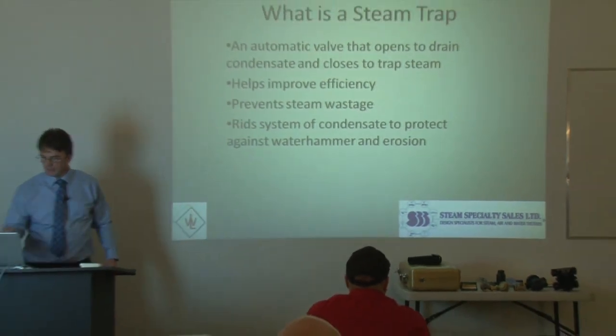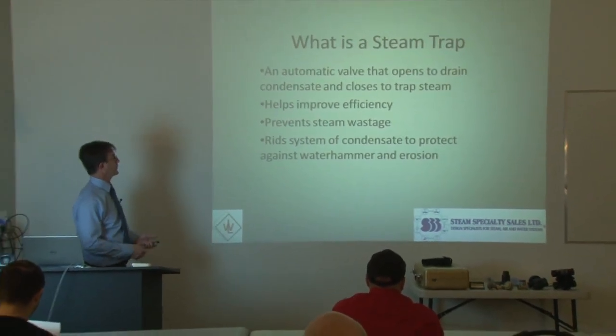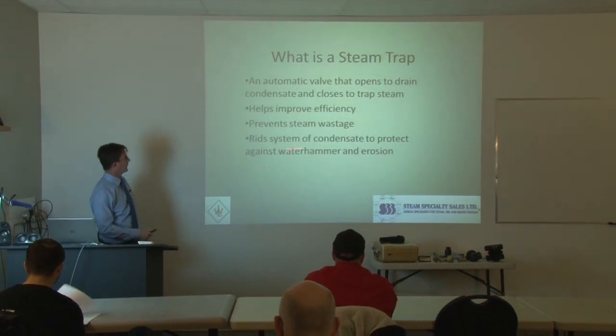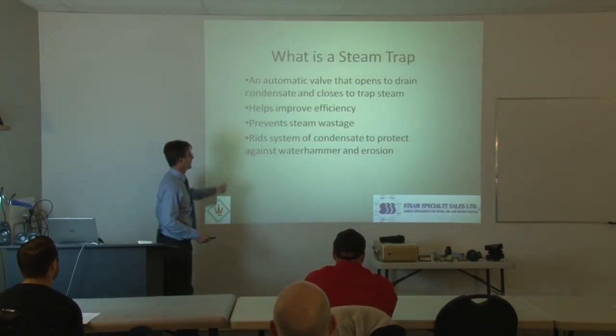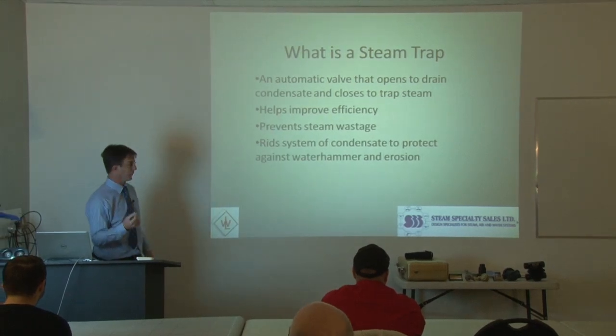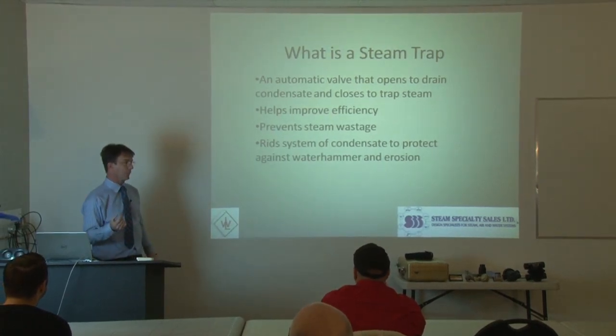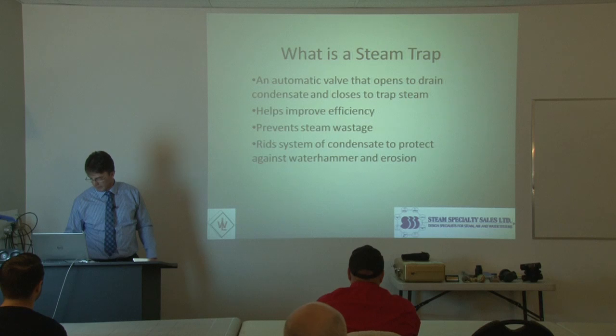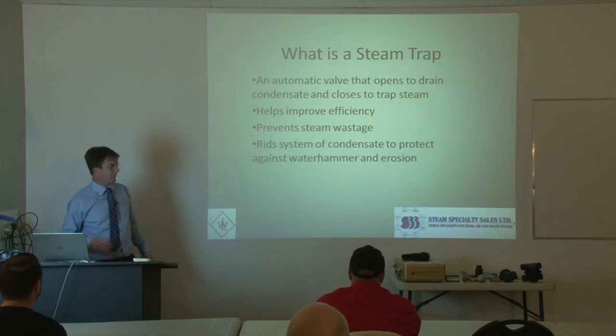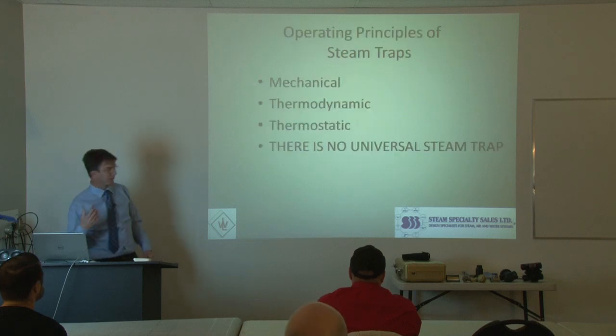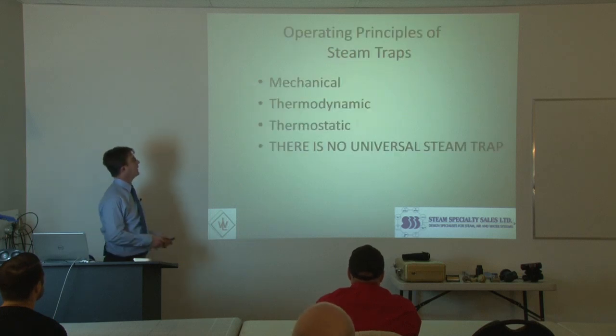Steam traps also help improve efficiency, help prevent steam wastage, and rid the system of condensate to protect against water hammer and erosion. A lot of times we hear water hammer and think it's normal — it may be common, but it's not something we should be hearing. A well-designed system, properly maintained, you should never hear any type of water hammer or pinging or banging in the pipes.